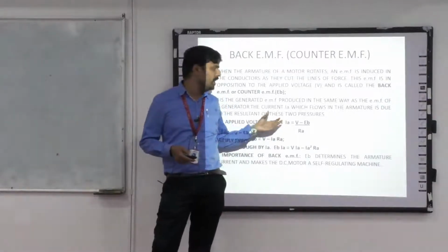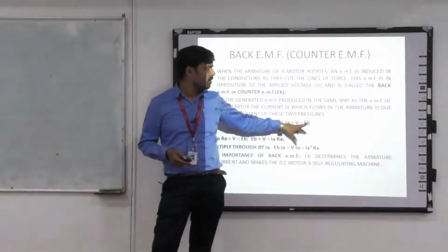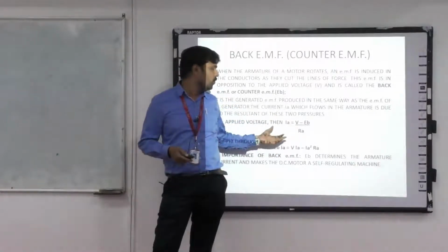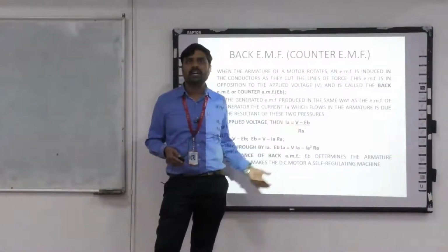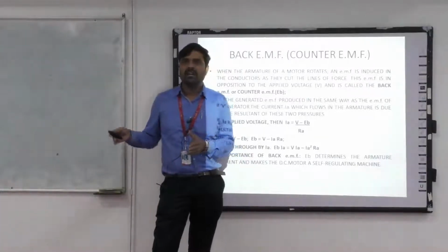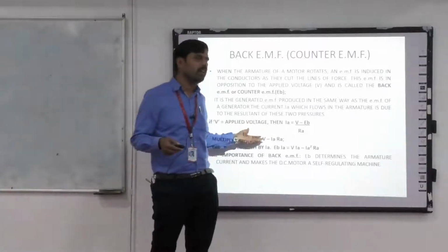Suppose, for example, we are using a 230 volt motor. 230 volts is applied, right? The back EMF is 0. 230 divided by 0.5 gives 460 amps. But the motor cannot withstand such a high current because it is designed for 12 or 15 amps. If 460 amps flows, what happens? The coil gets burned and the motor will be damaged.